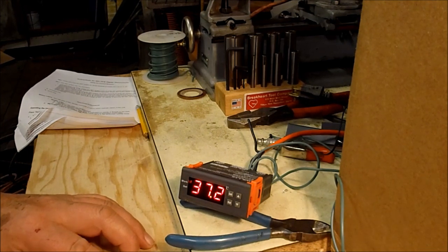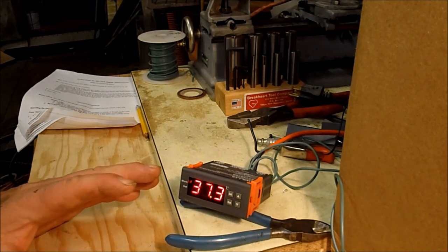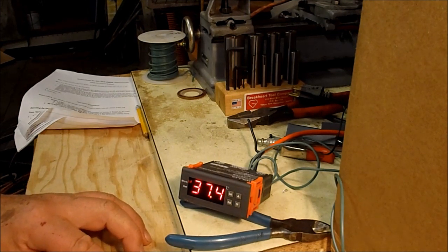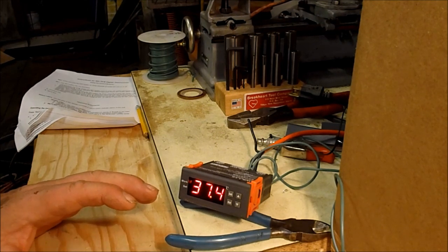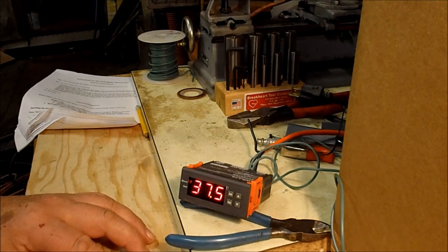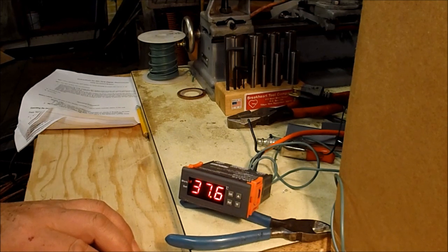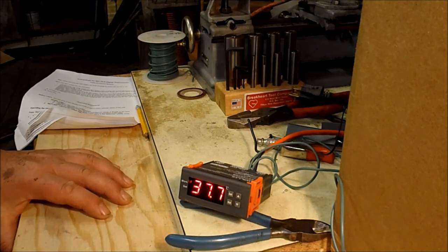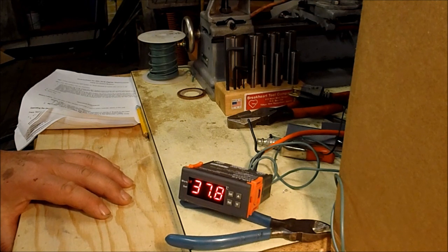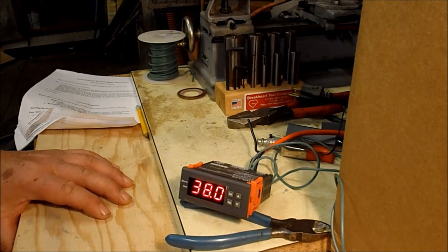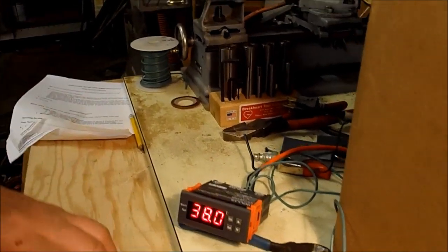Then the temperature will decrease down to 37 degrees, and then the switch will click and that will close the circuit and the light will come back on. Same thing if you were using a heater, same thing if you're using an air conditioner or a refrigerator. Okay, there was an audible click at 38 degrees and the light is shut off.